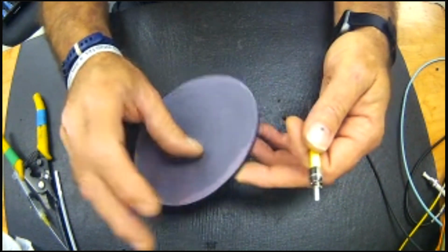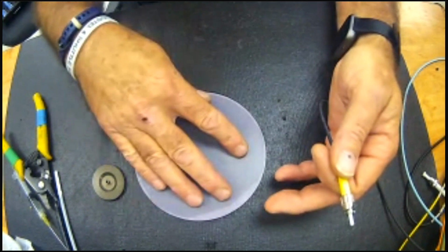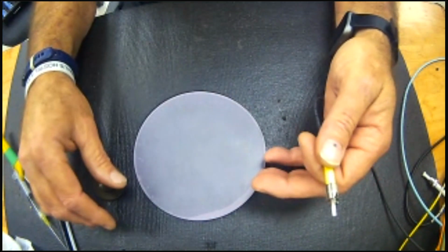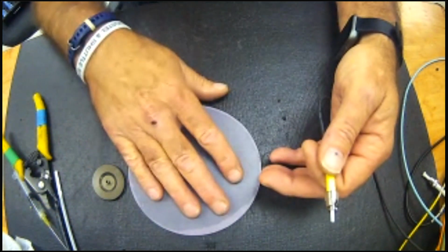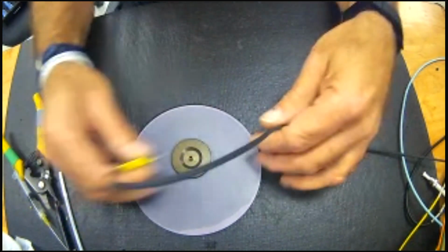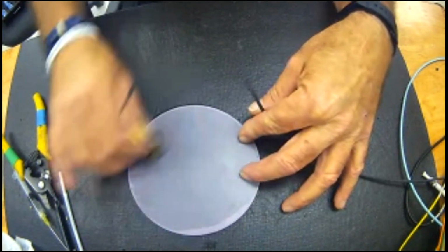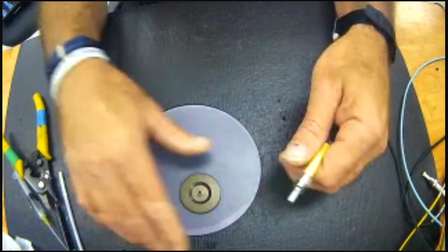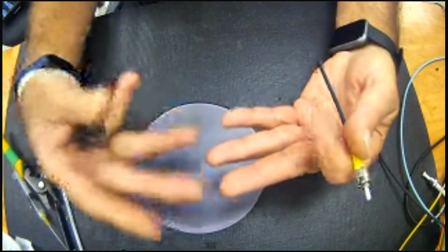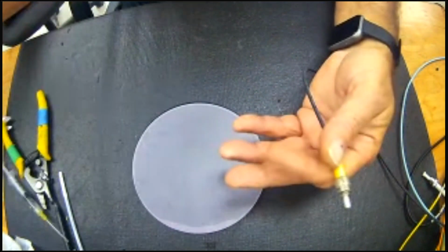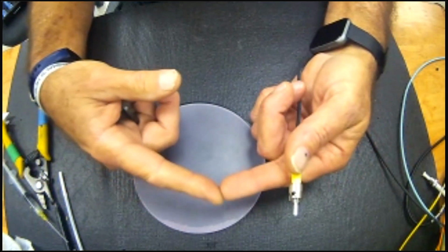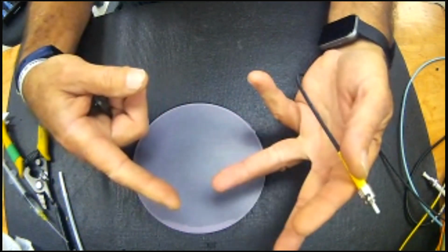I spend the money, I buy the $5 diamond films. I get hundreds and hundreds of uses out of it. Water is your only lubricant, and the same thing. Simply figure eighting, 8 to 10 passes. In my case, my preferred polishing technique is 15 micron, and then I use diamond film, and I go from a 6 to a 1 to a half.